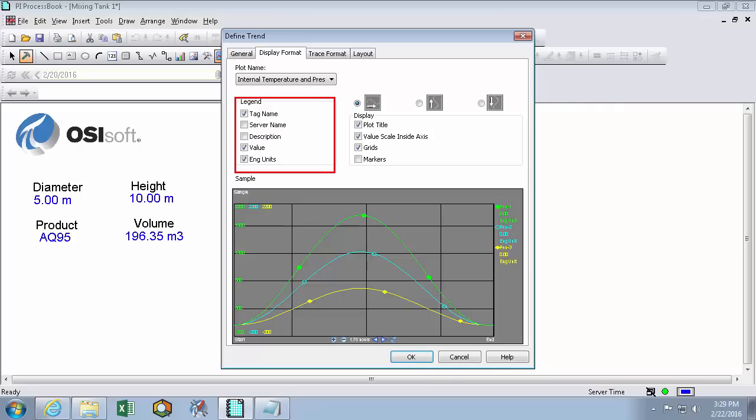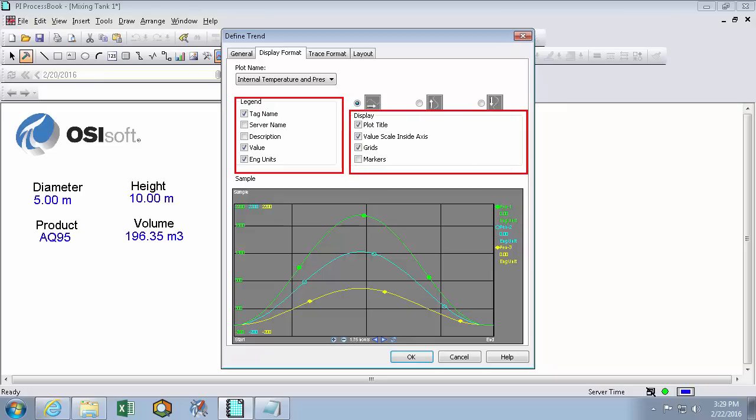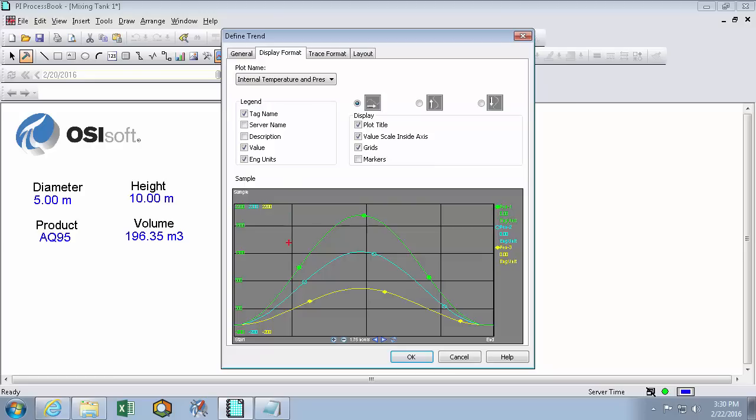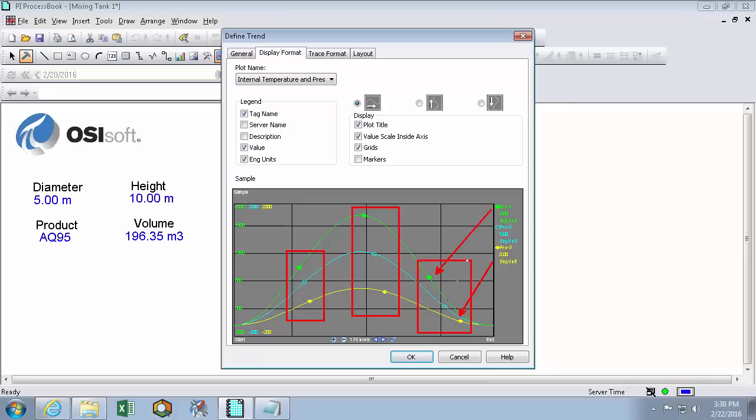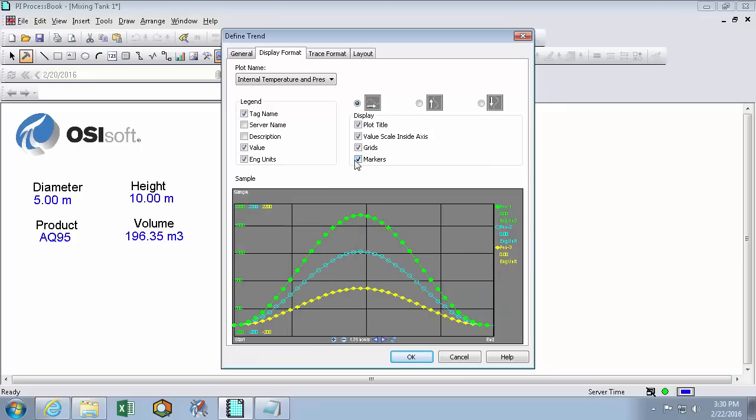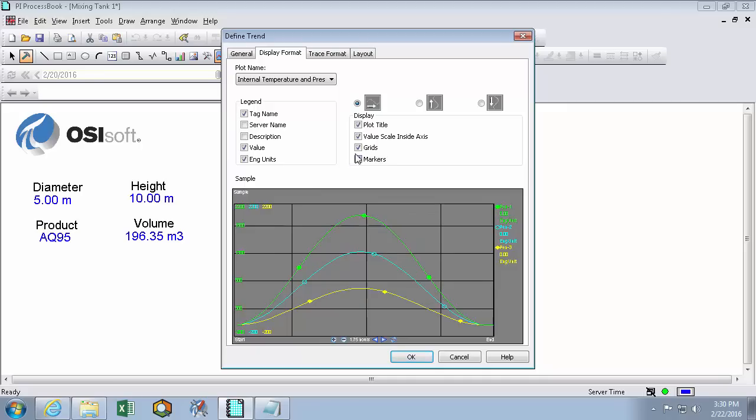And now we can choose the display format of our trend in the second tab here. So we can choose what's in the legend and what's not in the legend, as well as what's on the trend and what's not. By default each trend has three of these markers on it, and they're there so you can tell which color ends up with which trend element. If you check the marker icon, you'll actually see a marker for every single data point that's in the PI data archive. And since that's going to be a little bit too busy for this trend, we'll uncheck that so we can see the three per line.